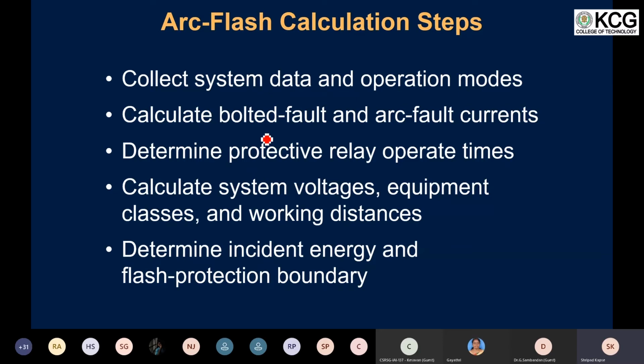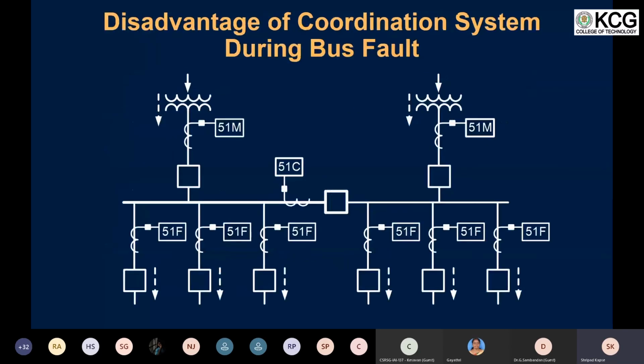And then we need to determine the protective relay operating time and other equipment related information, like the type of chamber in which this arc flash hazard may occur and the kV level of the switchgear. Based on all those things, we determine the incident energy and the proportional arc flash boundary that could occur.